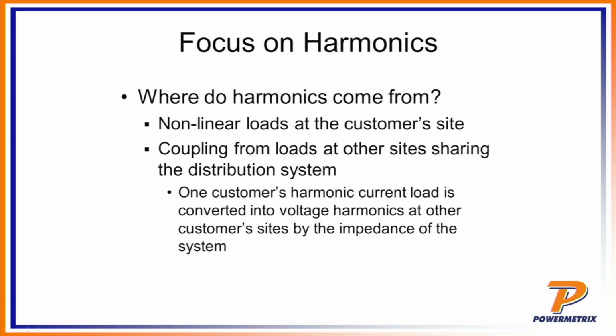One of the problems with harmonics is that it sometimes can couple due to the loads to different sites sharing distribution systems. In other words, if you have one customer that has a really bad load that generates really bad harmonics, sometimes that can cause those harmonics to be transmitted back to other customers. And as such, that's where you as a utility may have to go out to the customer and say, hey, Mr. Customer, we're going to have to do some sort of power quality analysis to figure out what your problem is, either that or put it back on the customer, have them do it. A lot of times the customer may have to install a filter or something to be able to prevent that from getting back out into the system and affecting other people.